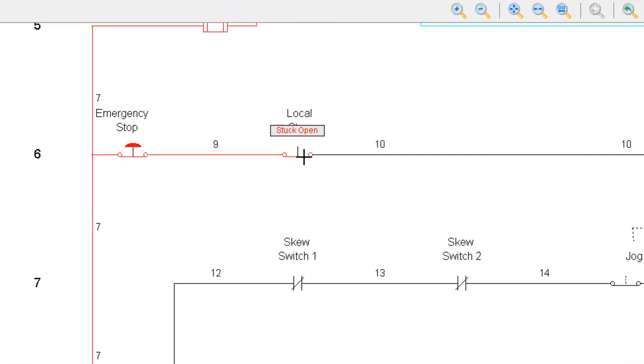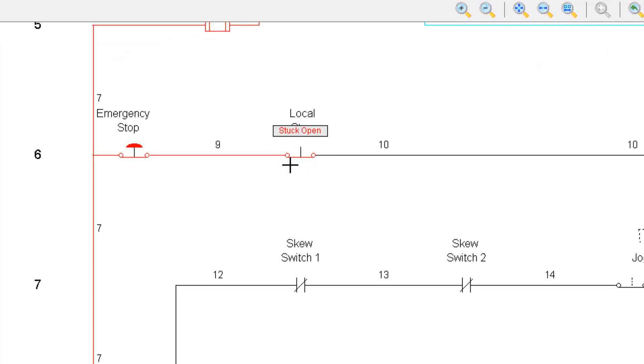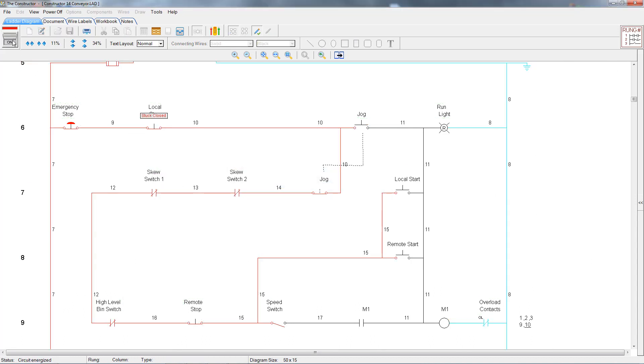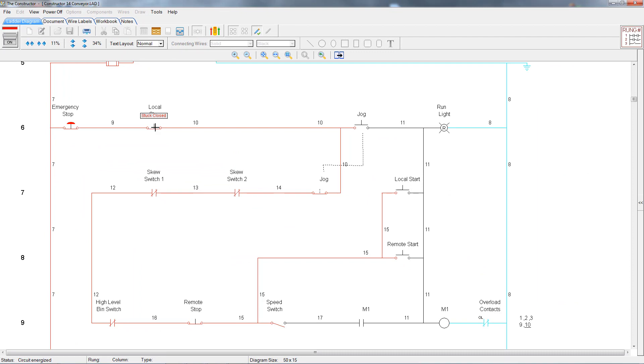Even though the contacts visually look closed, the power does not run through it. Now we'll change it to defective contact stuck closed and try it again. Now it appears to be working correctly because the power is flowing through it, but when we push on the button and open the contacts, the power still flows through it. That's because the defective modes affect it electrically and not visually. This makes the troubleshooting mode more realistic because in real life, you may be pushing on the button and it may appear to be working, but electrically it is not.